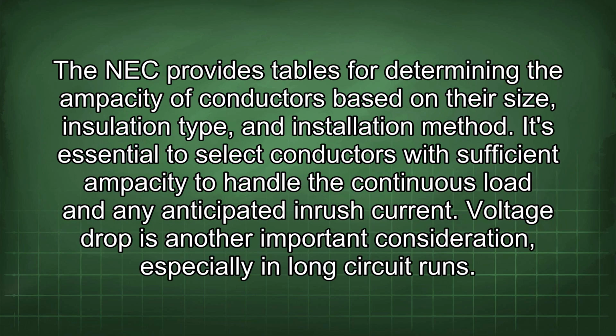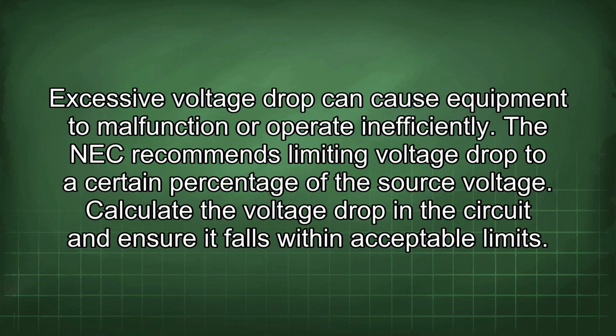The NEC provides tables for determining the ampacity of conductors based on their size, insulation type, and installation method. It's essential to select conductors with sufficient ampacity to handle the continuous load and any anticipated inrush current. Voltage drop is another important consideration, especially in long circuit runs. Excessive voltage drop can cause equipment to malfunction or operate inefficiently.